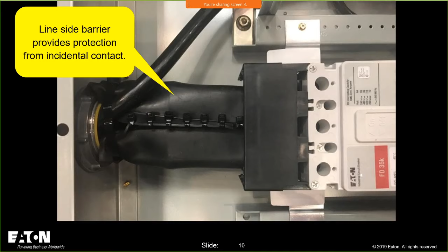Right, so the barriers shall be placed in service equipment such that no uninsulated, ungrounded service bus bar or service terminal is exposed to inadvertent contact by persons or maintenance equipment while servicing load terminations. Right, so again, this is all service equipment. So I don't care. Some people will say, "Well, what about my whatever this is?" If it's listed as service equipment, you are going to have that barrier.